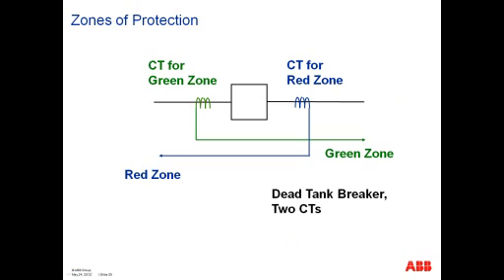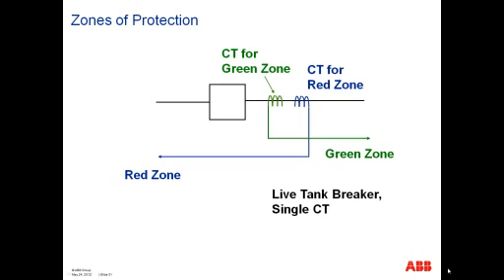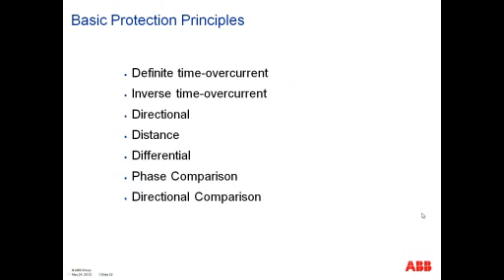All right. And if we notice that as we did this overlapping, it says CT for red zone. It's not very red, but anyway. You have the CTs that are going to be protecting a zone on the opposite side of the breaker. That is the normal convention. The normal way a dead tank breaker at least would be applied. Next slide.